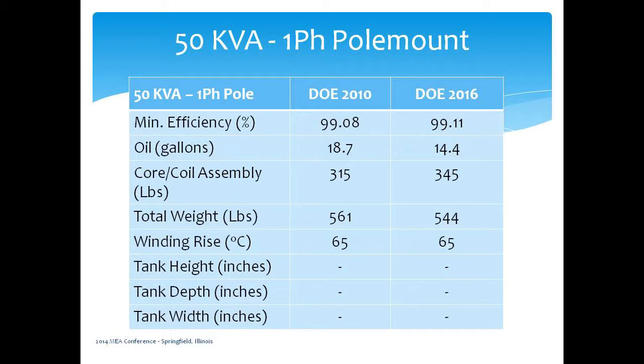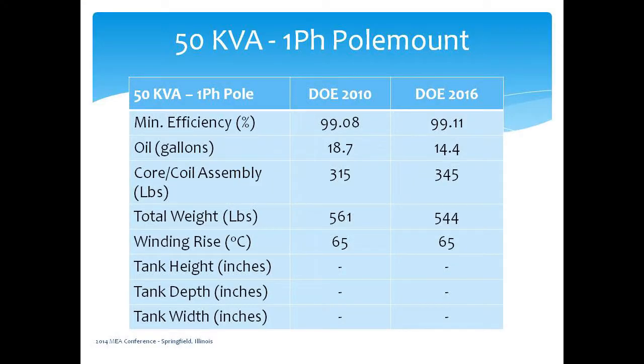But you can certainly see the impact. It drove down the amount of oil from 18.7 to 14.4, but look at the core coil assembly weight. And I couldn't get the physical dimensions on this one, I apologize for that, but you can see where the total weight actually goes down in this particular case. Why? Because the tank size actually went smaller, so we're able to use less oil, with less displacement, and fit in a smaller tank. And notice that the temperature winding rise, 65 degrees C, is pretty close to the ANSI max on the design of it.